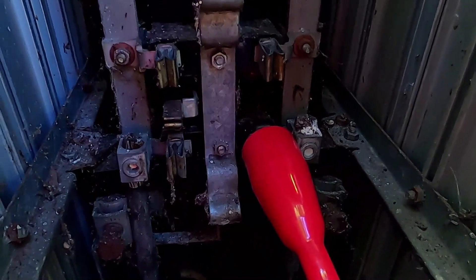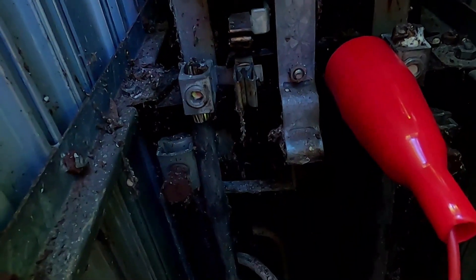Here's a close-up photo of what this looks like inside this meter socket, which they also call a power pedestal. We'll be back after we set up our tracing equipment to show you a bit more about what's involved in this troublesome repair. So we're inside the meter socket now — this is A phase and we're attached to B phase right now.